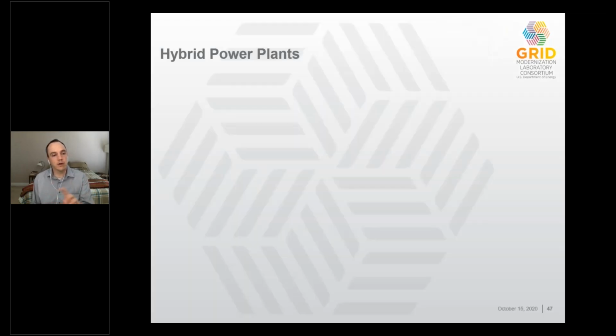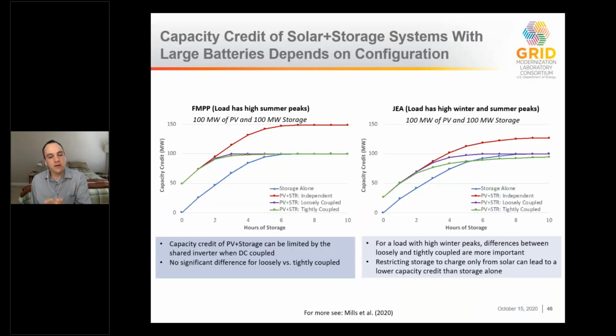The other interesting thing, if you focus on the chart on the right, is what we found with the utility in Jacksonville, where they tend to have high load in the summer, but also very narrow, high winter peak events that happen when a storm comes through and there's a lot of electrical heating demand that spikes up. In that case, if we restrict the storage to only charge from solar, the tightly coupled case shown in the green line, we could end up with situations where during these winter cold weather events the solar would be insufficient to charge the storage, actually lowering our capacity credit to some degree.